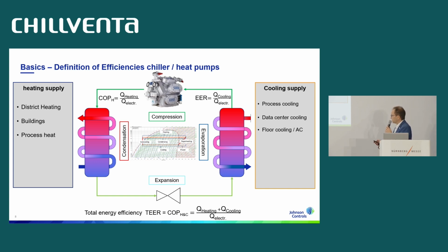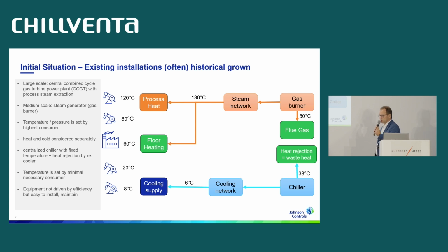But now to the very easy steps. Again, the initial situation at our customers coming from industry: we always have the same installations, and typically they are historically grown. In large-scale industrial solutions, we have a central combined cycle gas turbine power plant and steam extraction, to feed a steam network to fulfill process heat demand, for example at 130 degrees Celsius. In a medium-scale industrial solution, this is simply a gas burner. The pressure and the temperature of the steam network is typically set by your highest consumer.